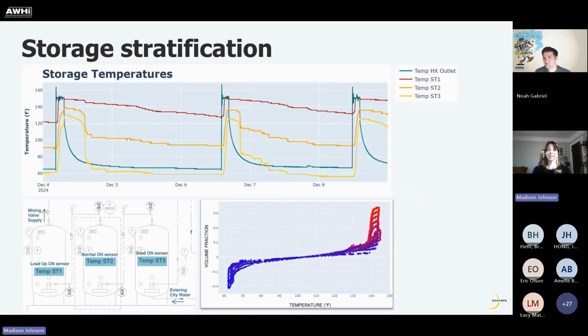So in the table with the Portland demonstration, we saw that Ecosizer engine predicts higher thermal shift capacity than what we saw in the single draw test. This discrepancy is primarily driven by the stratification profile in the primary storage tanks. Ecosizer engine assumes perfect stratification, which means that the entire hot zone of the tank, or everything above the aquastat, is equal to the heat pump water heater set points. We know from field data and just from the control logic that when the heat pumps turn off, the lower zones in the tank are cooler than the heat pump water heater set point.